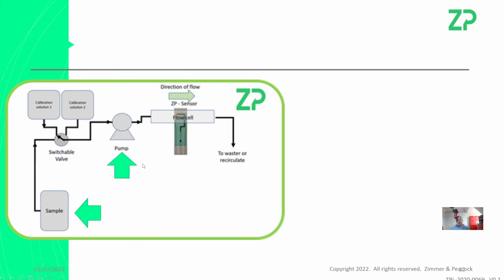You have a pump, for example a syringe pump, and it's actually pulling samples from the reactor. I prefer mode 3 because in mode 3 you've actually had the sensor in the sample at all times, but there's a problem which I will bring up. But mode 4 overcomes the problem.